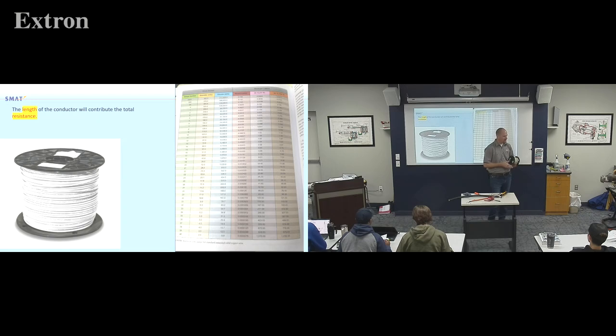might have used 100 foot off the roll, and they got to go pull a wire, and the blueprint says, I need 400 foot of wire. And they go, I don't know if I have 400 foot on there, but I don't really want to spread all across the floor just to find out it's not and put it back on. So they'll go to a chart like this. This one's 12 gauge, I think we said. So they'll go to the 12 gauge, run it over, say, okay, it's 77 degrees outside. It should be 1.62 ohms per 1,000 feet.